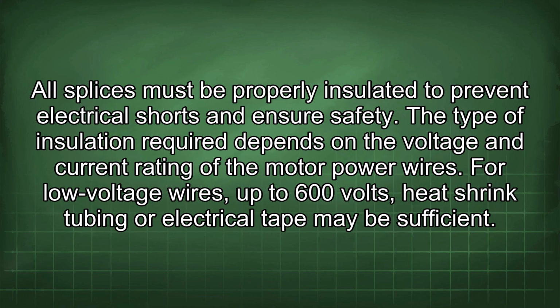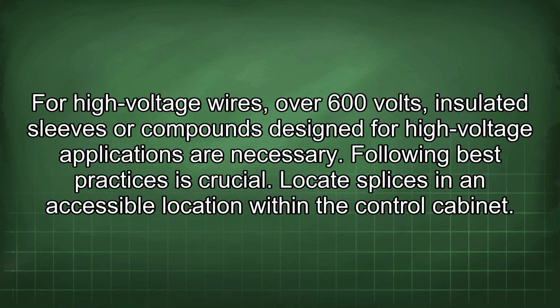All splices must be properly insulated to prevent electrical shorts and ensure safety. The type of insulation required depends on the voltage and current rating of the motor power wires. For low voltage wires, up to 600 volts, heat shrink tubing or electrical tape may be sufficient. For high voltage wires, over 600 volts, insulated sleeves or compounds designed for high voltage applications are necessary.